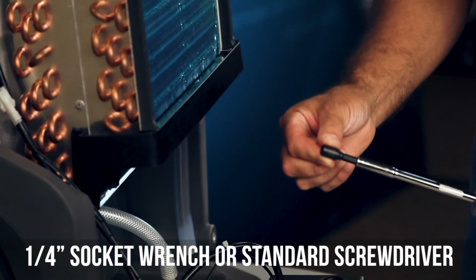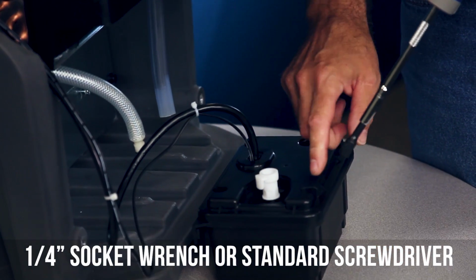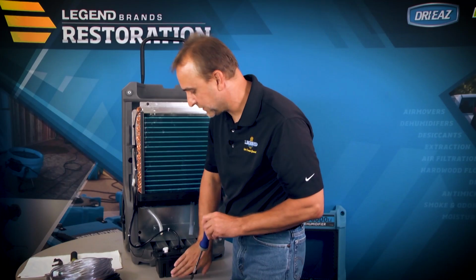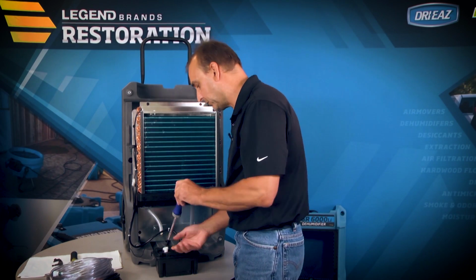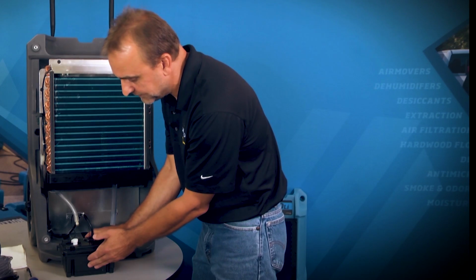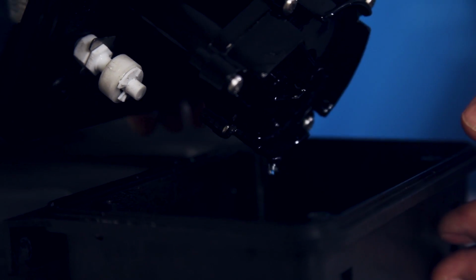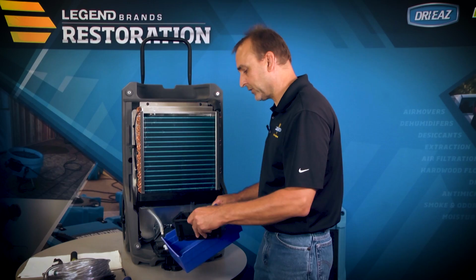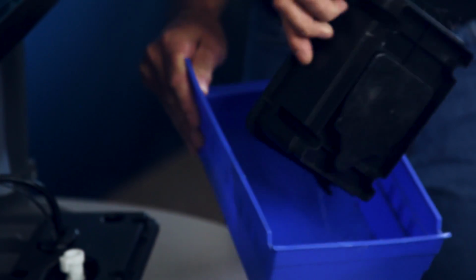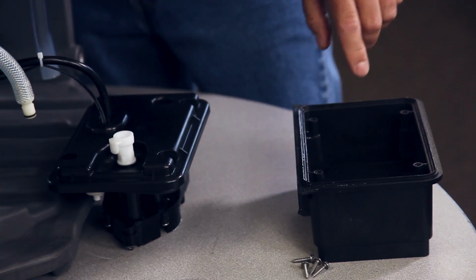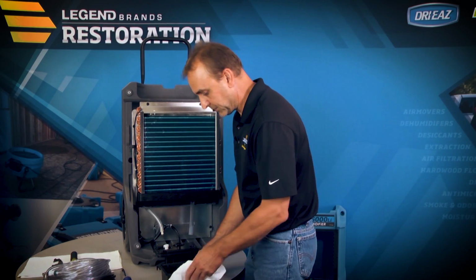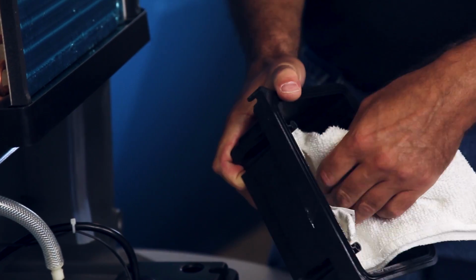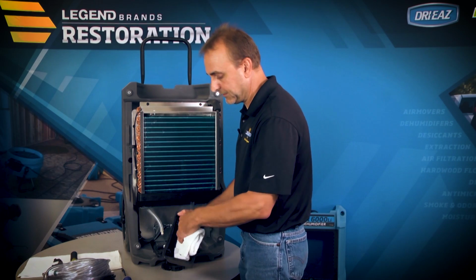To inspect the inside of the condensate sump, you'll need a 1/4 inch or standard screwdriver to remove 4 screws that secure the top cover to the sump. The screws are located near each corner. Now that the screws are removed, you may separate the top, which includes the condensate pump, from the sump. You'll want to clean the sump out with a soft cloth and inspect the top edge of the sump to ensure there aren't any chips or cracks. You may also use detergent or your favorite disinfectant.